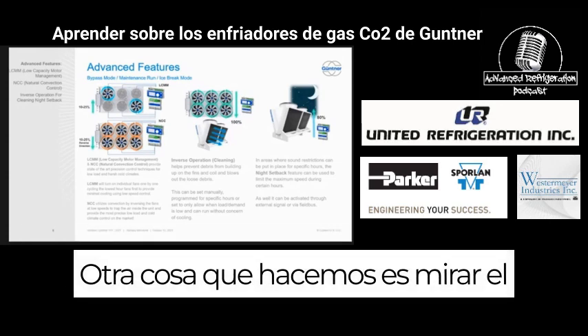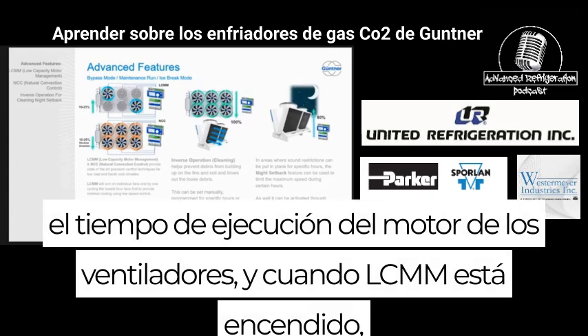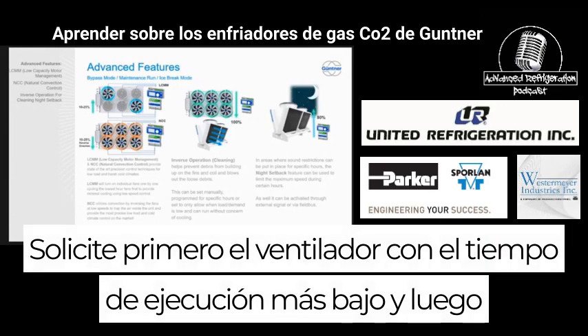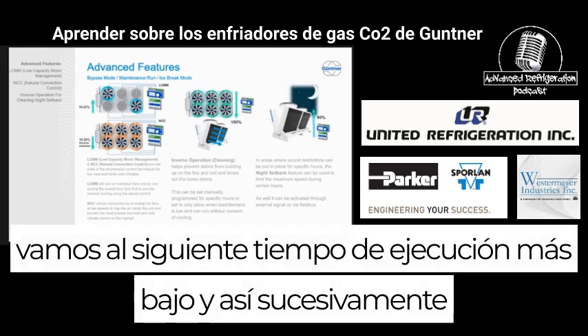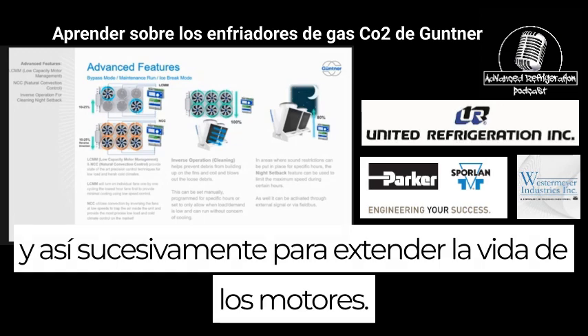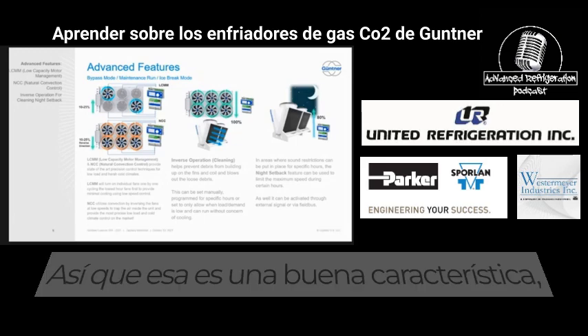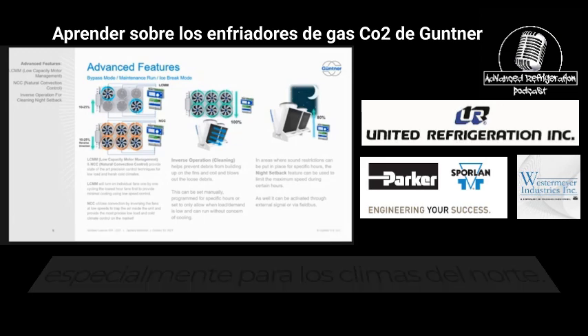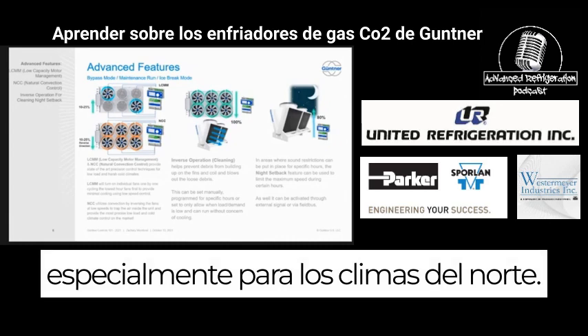Another thing that we do is, we look at the fans' motor runtime, and when LCMM is turned on, we request the fan with the lowest runtime first, and then we go to the next lowest runtime, and so on and so forth to extend the life of the motors. So that's a nice feature, especially for northern climates.